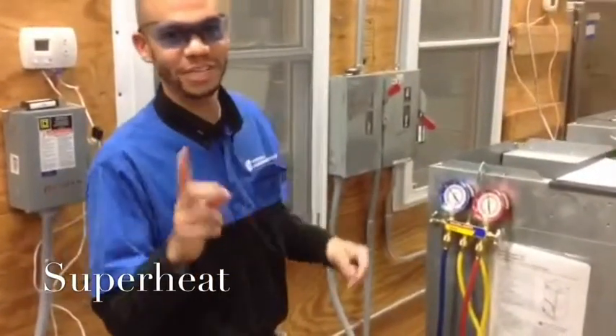I am Derek, your HVAC technician, and right now we're going to demonstrate how you do superheat. So, first we're going to determine our refrigerant type. Right now we're working with 410A. So, we'll just write down 410A.